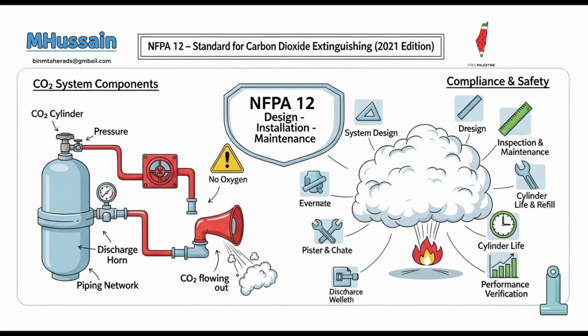The actuation sequence for automatic systems is also very precise. The sequence of events. A sustained fire alarm signal first activates pre-discharge alarms, which then trigger electrically operated pre-discharge time delays and more electrically operated pre-discharge alarms before finally actuating the CO2 releasing devices. Alarm, delay, alarm again, then release. Very deliberate. This staged sequence isn't just about complexity, it's a vital part of personnel safety, ensuring a clear warning and time for evacuation before discharge. Safety sequence? What about the devices themselves?